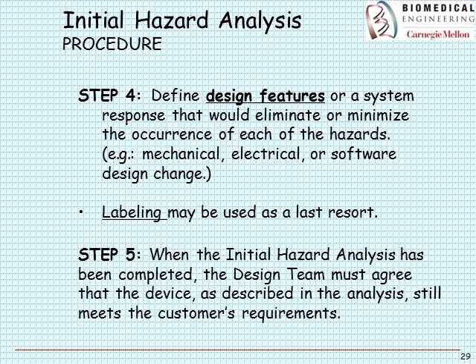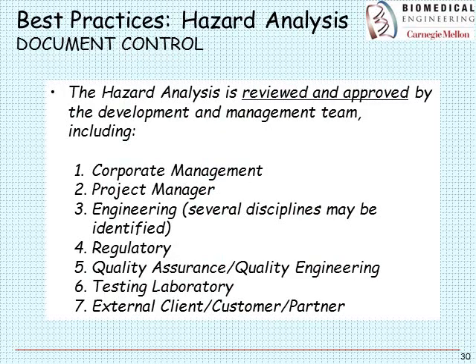Labeling is the last resort. Once the hazard analysis is completed, you need to assure the device still does what it was intended to do — that you haven't designed out its useful functions. The design team must agree the device as described still meets requirements. This is part of best practices. It's a controlled document, reviewed and approved by development management, signed off at many different levels. It's really serious business, and unfortunately there isn't much guidance on how to create that list of hazards.